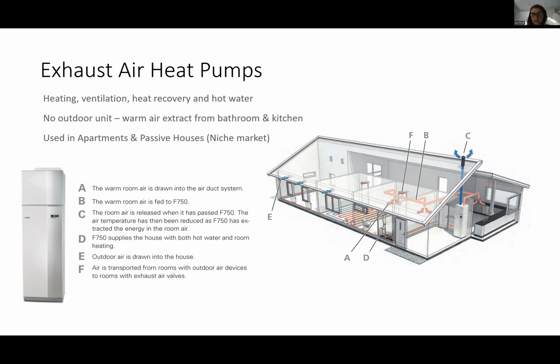So the way they work is, instead of being connected to an outdoor unit, they extract the warm air from bathrooms, kitchens, utility rooms. And that's used as the renewable source to provide heating and domestic hot water for the apartment or the building. So passive houses would use this type of technology. They have done for years.